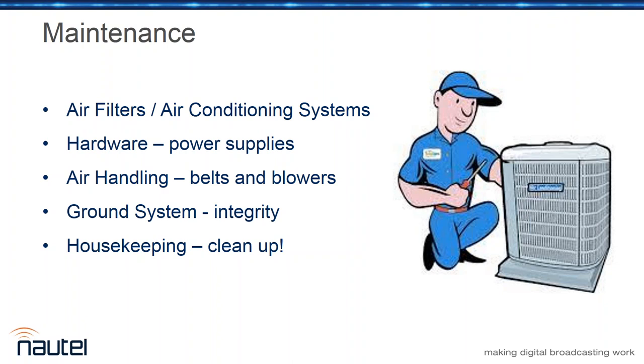At the very least, air filters should be done on a regular basis. Check the hardware, especially in power supplies. If you're working on an AM, check the filter and phasors, ATUs, things like that. Anywhere you've got stranded wire connections, there's potential for things to work loose. Anywhere you've got heating and cooling, daytimer AM where your transmitter's on some of the day and off some of the day, those things can work loose. Check air handling, belts and blowers, ground system integrity, and general housekeeping.